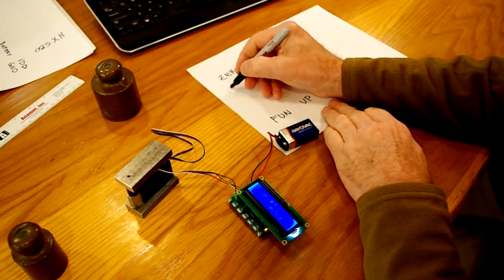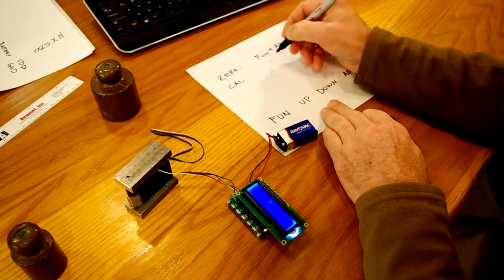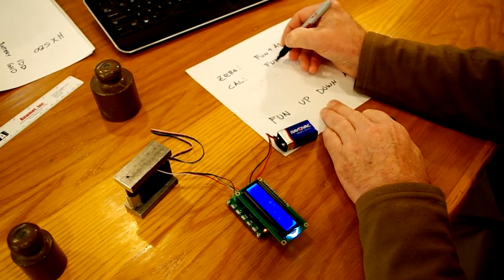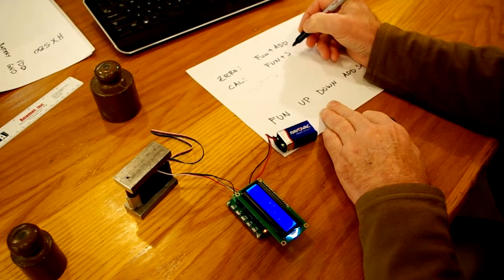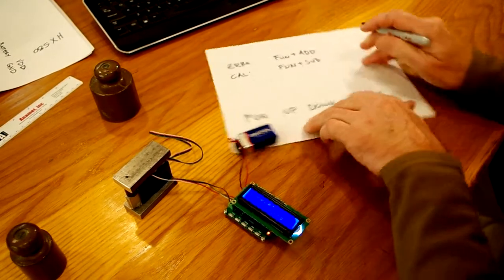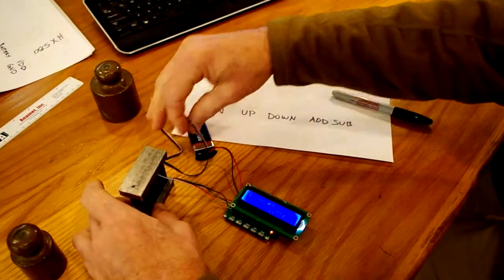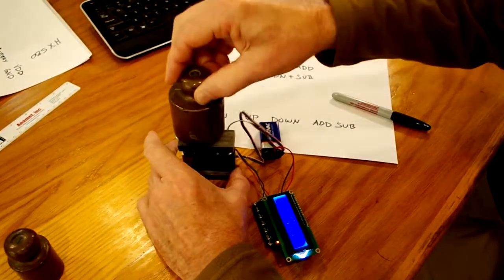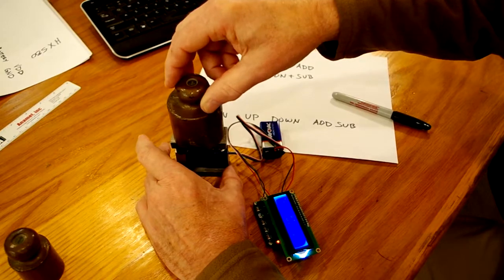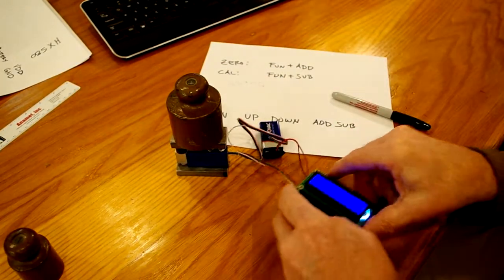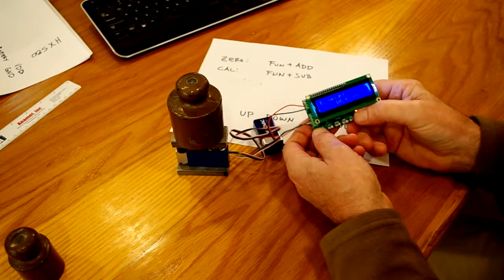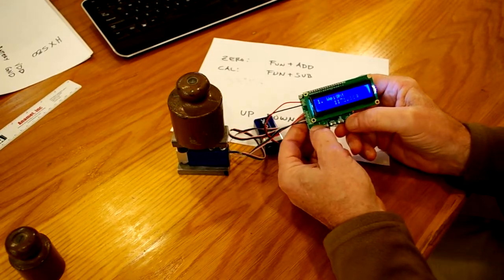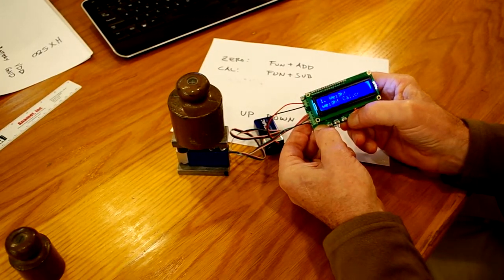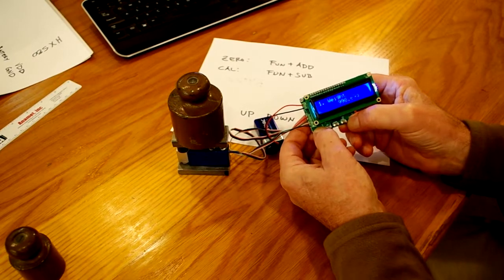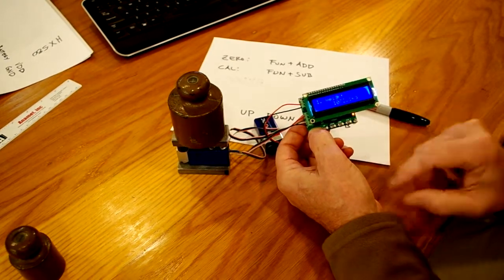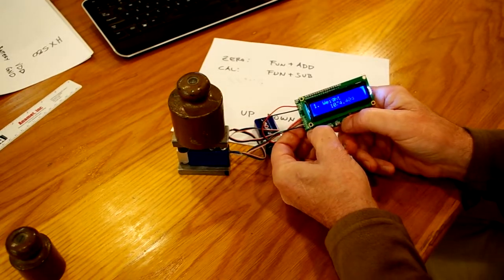Next we can calibrate it. For calibration, you're going to press the function plus the subtract key. So we're going to put our calibration weight on here. This is 1 kilogram. We're going to try not to vibrate here too much, so I'll push the function and subtract and let go. Pretty close. I'm off a little bit. I could redo that.